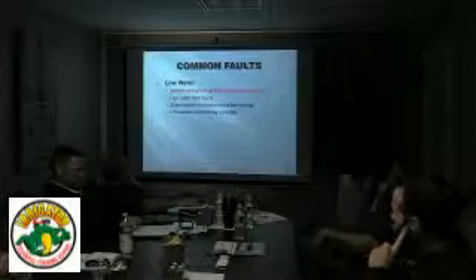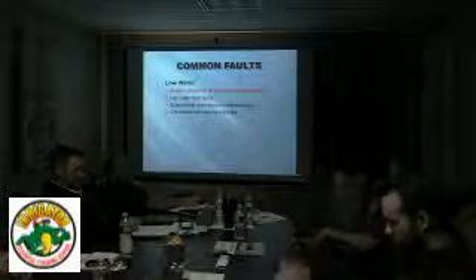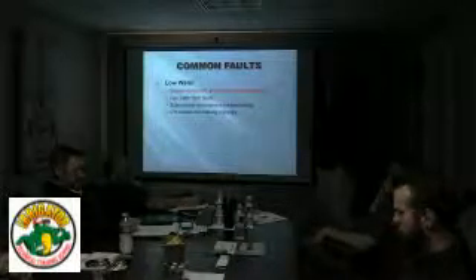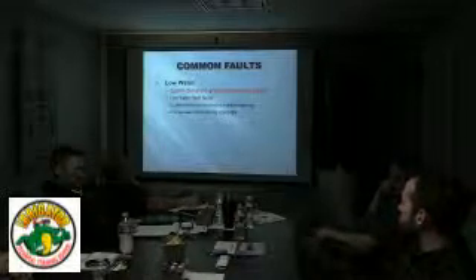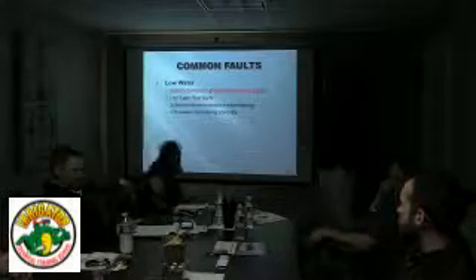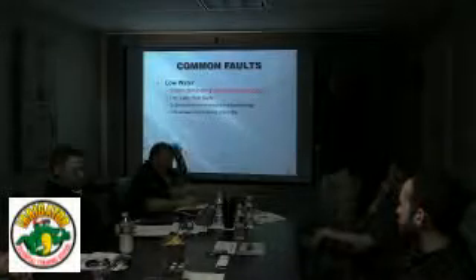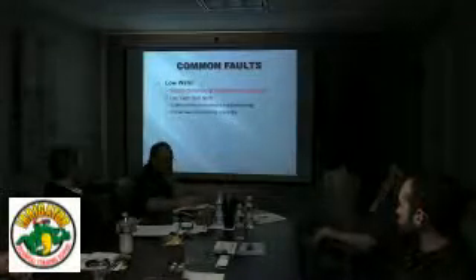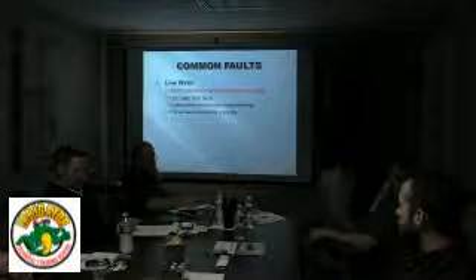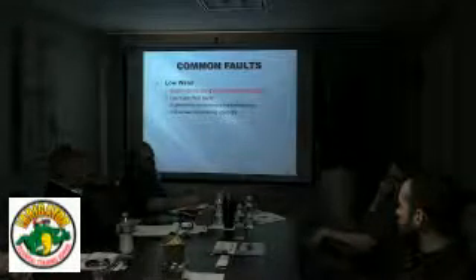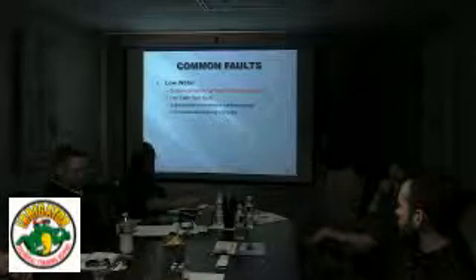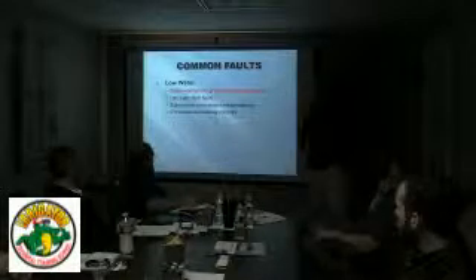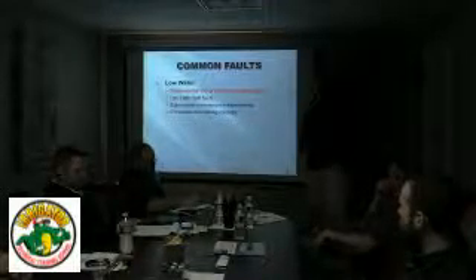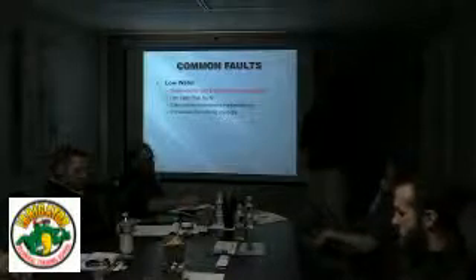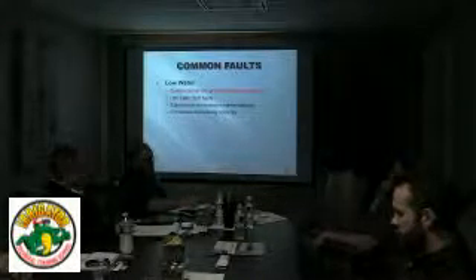Low water, system demand is greater than the supply. We see this occasionally. A lot of the canal companies around here put in weirs and only allow so much water. Subdivisions all like to water at 2 or 3 o'clock in the morning, and so if you're overusing what's coming in, you might see a low water fault if the system demand is greater. If you do get a low water fault and the water in the vault is up to normal level, it could be because that's happening. Now everything's normal when you come back on site and take a look at it.